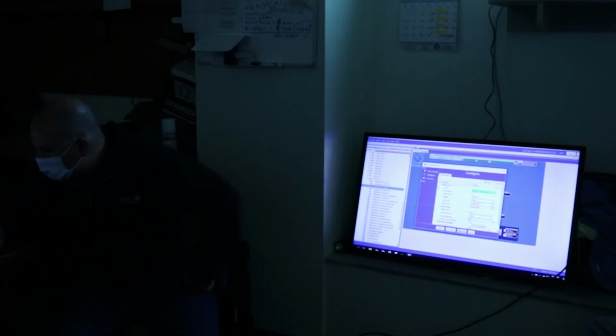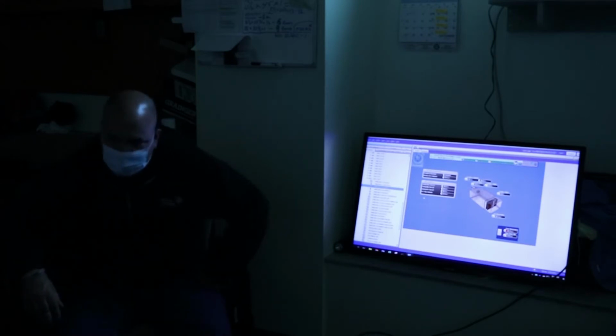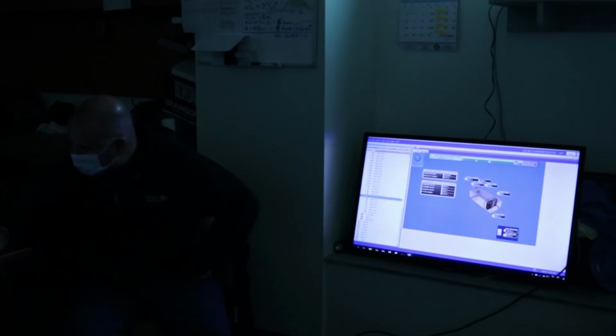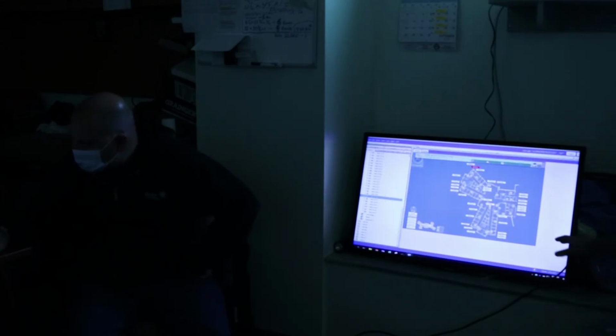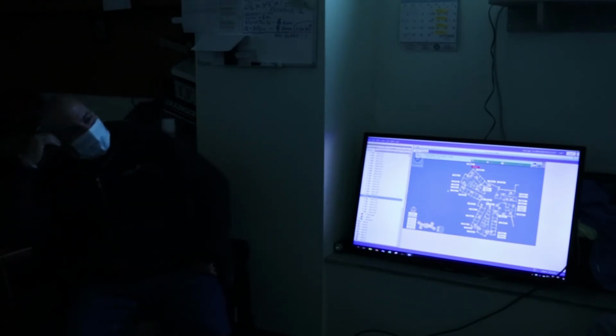So we're going to add a trend, we'll leave this every 10 minutes. We'll leave a trend on that, so maybe tomorrow we'll take a look at it and see what it did over the course of the day. It's definitely not enough here to go in this room. I would say most likely that's what it is, but until I get up there and look to see if there's any kind of other circumstance on it.